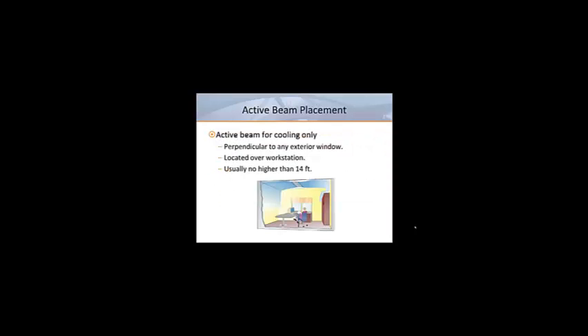When active beams are being used for cooling only, they should be placed perpendicular to any exterior glass. Unlike passive beams, the best location is directly over any work area or stationary occupants. Since active beams discharge air like conventional ceiling diffusers, this placement provides the highest comfort.